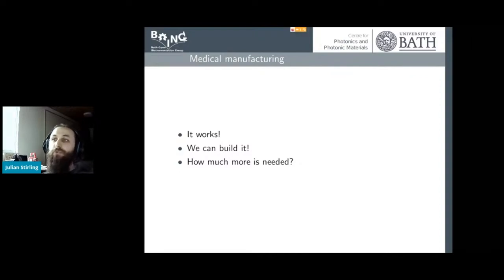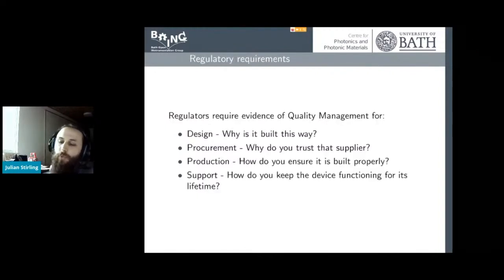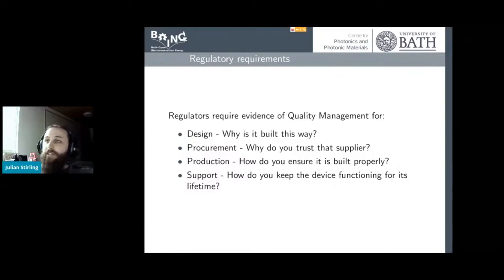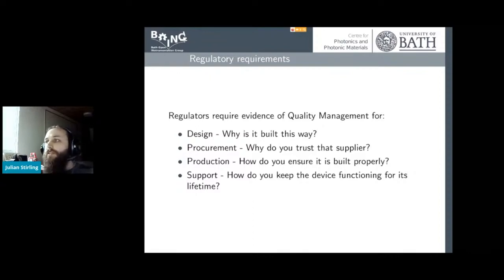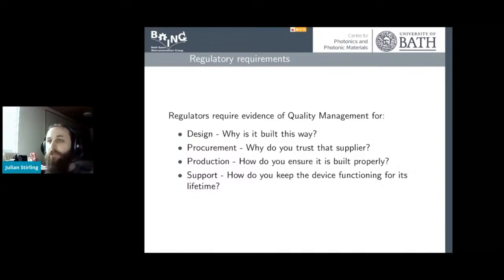It turns out there's a huge amount to go from something that works and something you can build, to something you can actually certify as a medical device. When I say certify as a medical device, we have to look into the regulatory requirements, which talk a lot about quality management systems. The quality management system covers the design: why was it built that way, what decisions did you make, why did you do this — and all of that has to be recorded to show you've got a quality process.